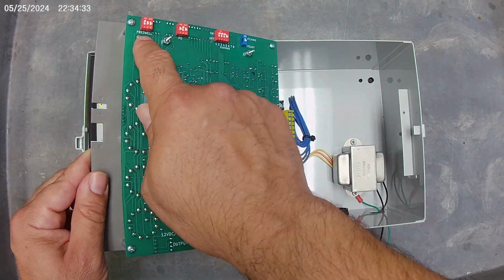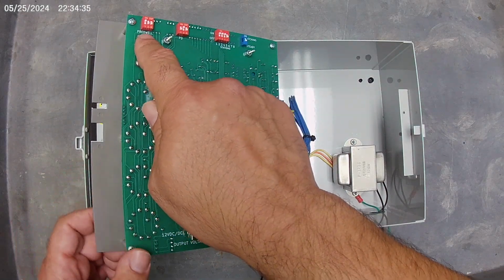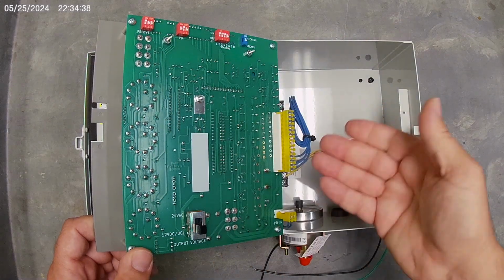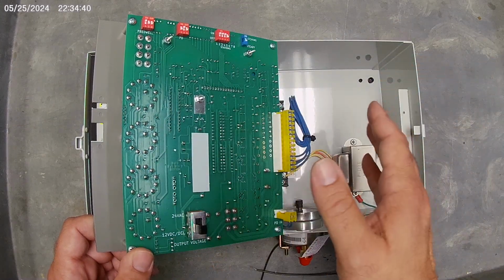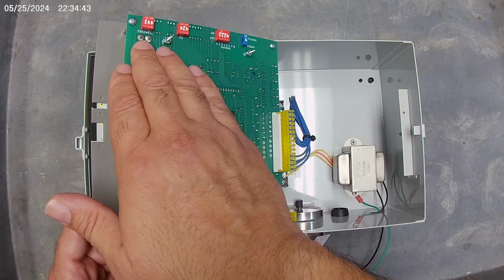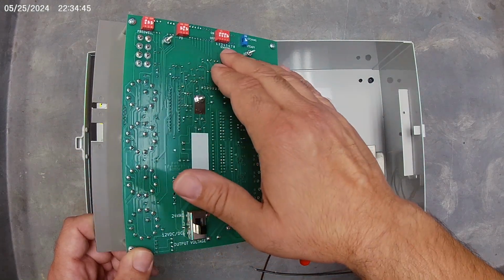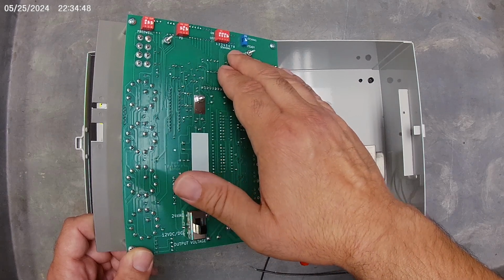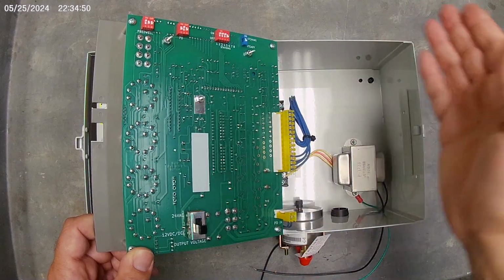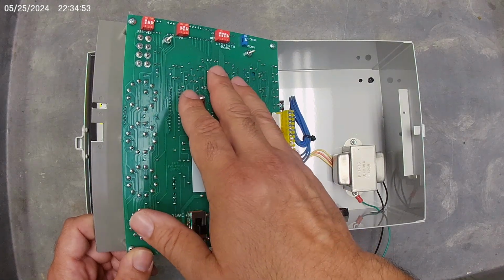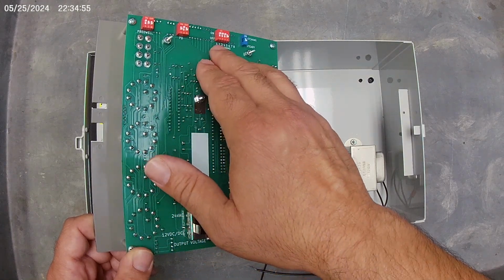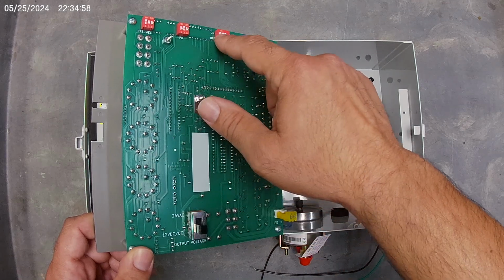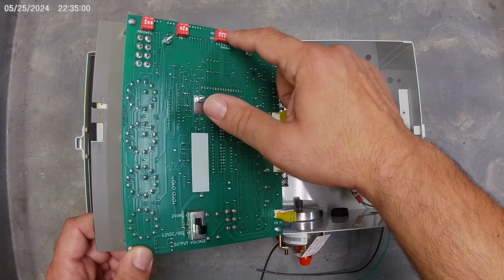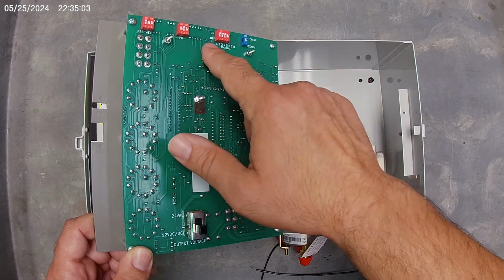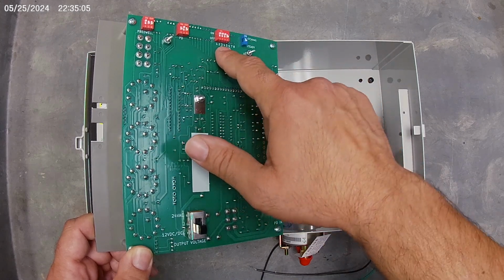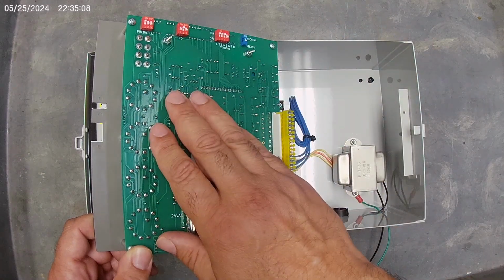Pre-dwell you need if you have a pressure sustaining valve in the system, and that gives time for that to close to build pressure to flush the system. If you do not have a pressure sustaining valve, that can just simply be left off. Our station selectors here determine how many stations the controller will step through before returning to idle. This happens to be a 4-station controller, but if we only had 3 stations, we would simply turn the first 3 switches up, leaving the 4th down, and when it gets to station 3 and finishes the flush, it would go back to idle.